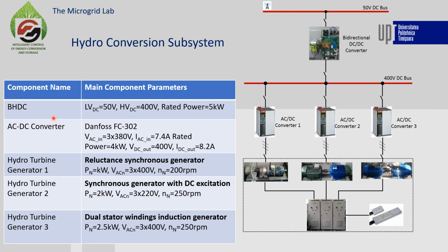Each generator is connected to an AC-DC converter, which injects the produced power into the high voltage DC bus. These converters are from Danfoss, but their control board was replaced with another interface card that provides full control over the inverter IGBT gate drivers, allowing us to develop new control strategies.